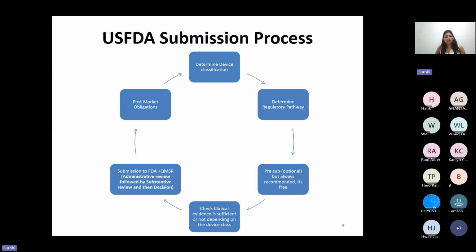After all this is done, the work doesn't stop here. Post-market obligations trigger in, and then all the requirements have to be met. For example, any implantable needs to follow tracked device guidelines and so on, vigilance, etc. Some manufacturers do go for MDSAP. If you go for MDSAP, then potentially US FDA may not come and inspect, but by all rights they can come and inspect also.